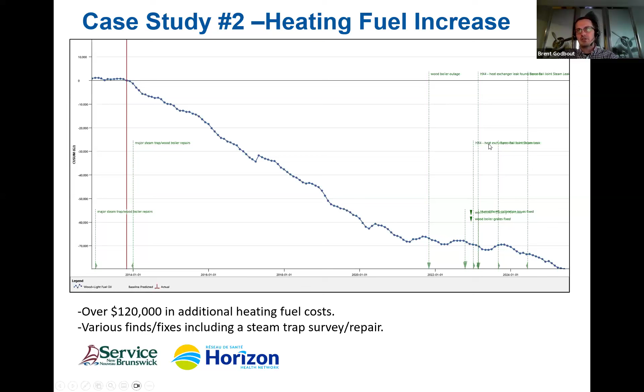Long story short, it took about 2.5 years until we finally found a 125 PSI main steam line located in the boiler plant ceiling, 30 feet above the floor. Insulated line. This is before the fixes were made.